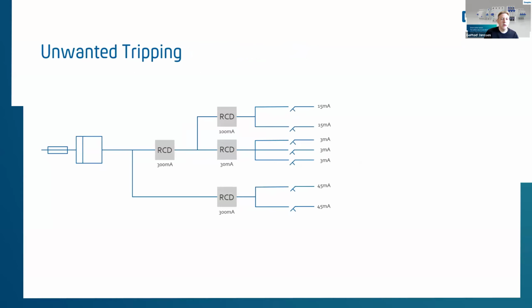So what is the solution to prevent the unwanted tripping and to have the right protection, fire protection or human protection? The right way to do it is to split up the whole installation. So you have one RCD in the mains, but if you go downstream, you have different RCDs splitting up the different single lines. Here it's 100 milliamp going down to the different lines again, 30 milliamp for human protection. So if you have small sockets which are being worked on by humans, then you should protect them with 30 milliamp. And there is another, for example, with 300 milliamp in a line to prevent fires. So the solution is to split up the whole system into different lines with different RCDs or different versions of RCDs.